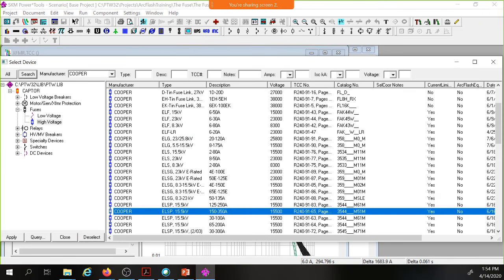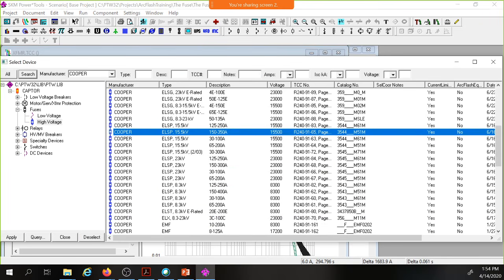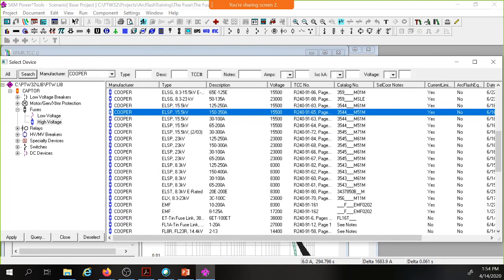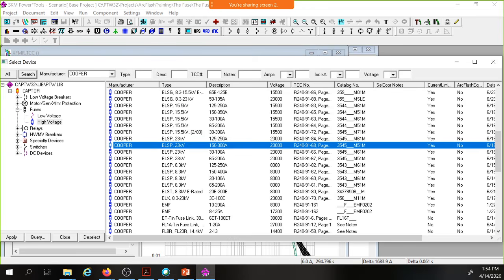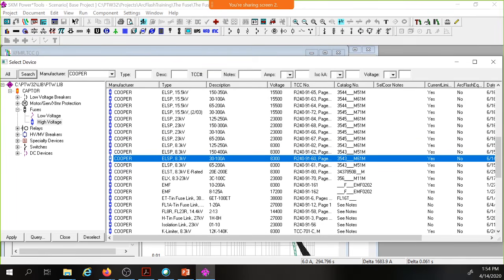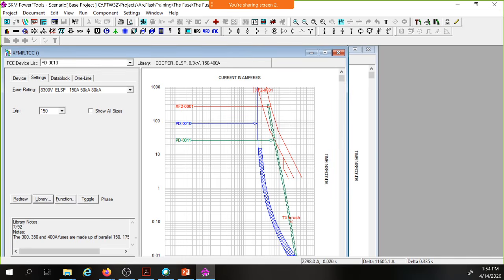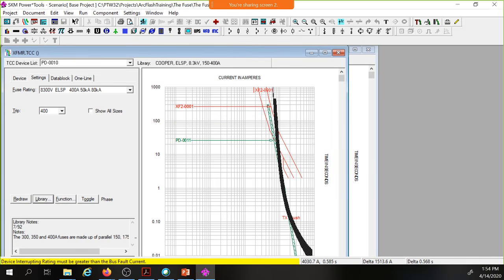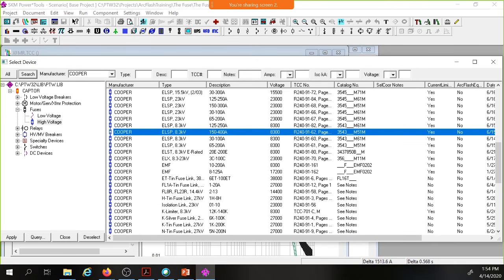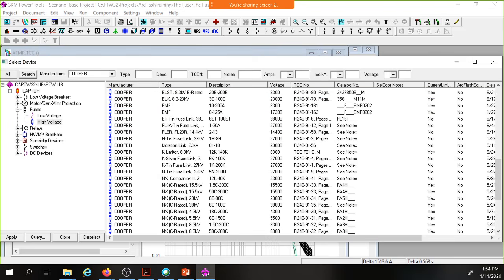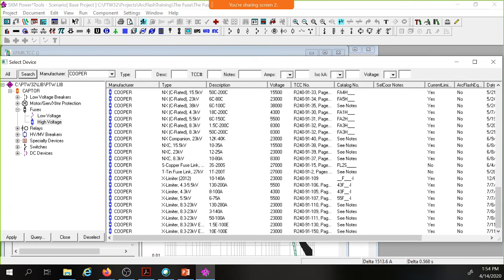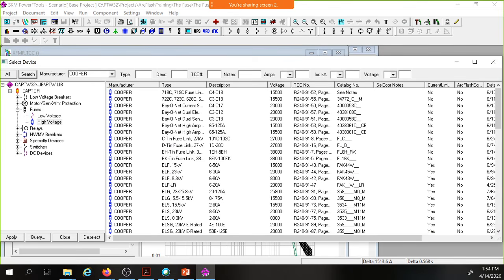Anyway, so that's basically what I at least wanted to show you, that damage curve and all the different options that are available. You have the different voltage classes, so you wouldn't need to go up that high on those specific voltages for a 4160 type of application. But again, you're worried about this transformer inrush. You don't want to open that fuse on the primary. The primary fuse usually is going to have something that's very sloped at the bottom. So that's basically what you're working with. And you got a lot of different options to pick that primary fuse.